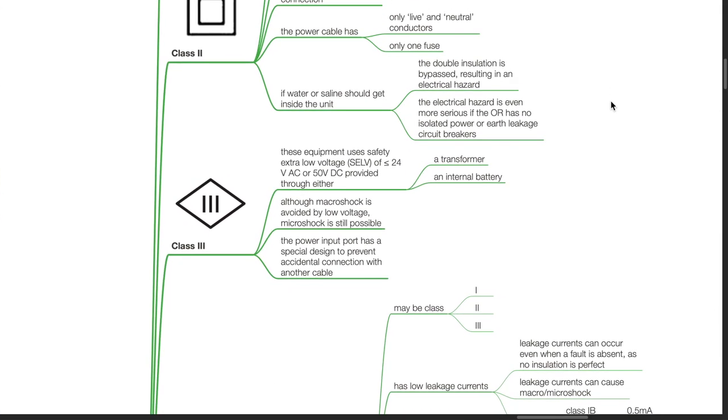Class 3 equipment uses safety extra low voltage of 24V or less for AC or 50V DC provided through either a transformer or internal battery. Although macroshock is avoided by low voltage, microshock is still possible. The power input port has a special design to prevent accidental connection with another cable.